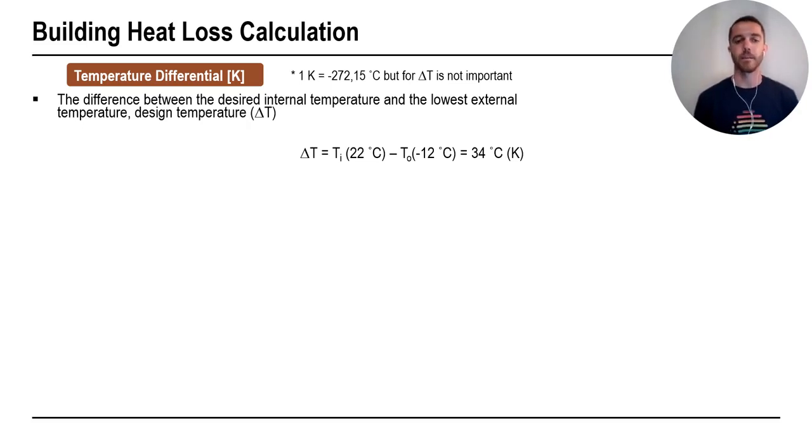So in this example, if we want inside temperature of 22 degrees Celsius, design outdoor temperature is minus 12 degrees Celsius. This temperature differential is 34 degrees Celsius, or degrees Kelvin. You need to take care of when you are dealing with Kelvin, as one Kelvin is minus 272.15 degrees Celsius, but here we are dealing with temperature difference. So temperature difference is the same in Kelvin and Celsius.